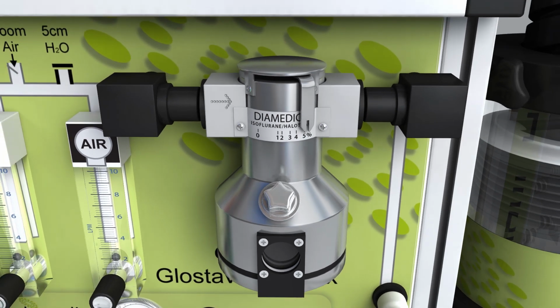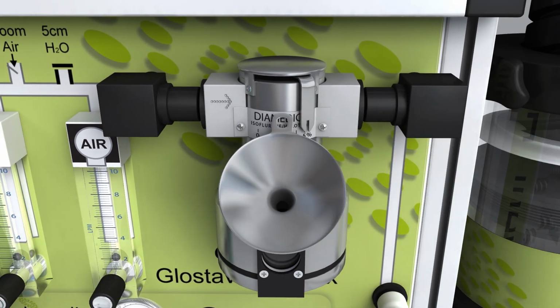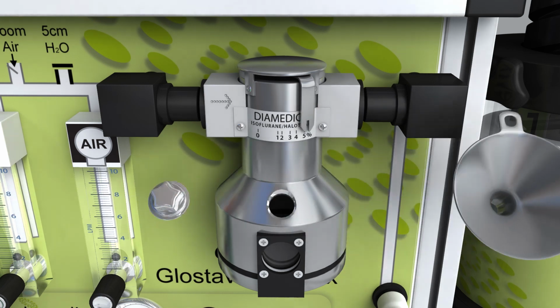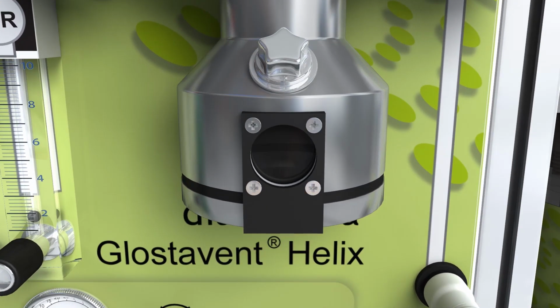The dual-agent vaporizer is calibrated for either isoflurane or halothane. The scale runs from 0 to 5%. It is filled by unscrewing the cap and using the funnel supplied. The vaporizer can hold up to 150 milliliters of anaesthetic agent, and the level of agent should always be visible in the sight glass.